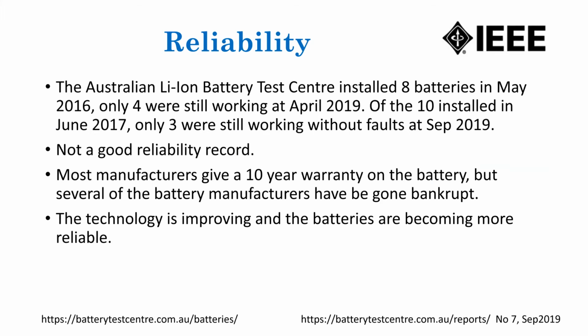The Australian lithium-ion battery test centres installed 8 batteries in May 2016. Only 4 of those were still working in April 2019, so the reliability of the battery systems at that time wasn't all that fantastic. Of the 10 batteries installed in June 2017, only 3 were still working without faults in 2019, and that's not a very good reliability.